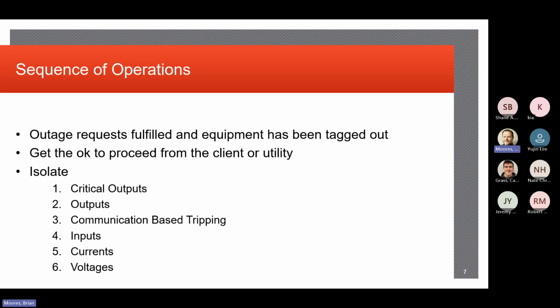If a relay is making a decision based on currents and voltages and the relationship between them, what might you isolate before you isolate voltages and currents? Let me rephrase it. If I opened a test switch for a phase A voltage, the relay now no longer sees phase A voltage, it goes to 0. What might that simulate? Might trip a breaker by mistake. Undervoltage. Oh, yeah, lost. So if you have a fault on a phase of a transmission line, what happens to the voltage? If you have a ground fault on a transmission line. Generally, the voltage collapses, right? So the voltage would collapse, go towards 0.